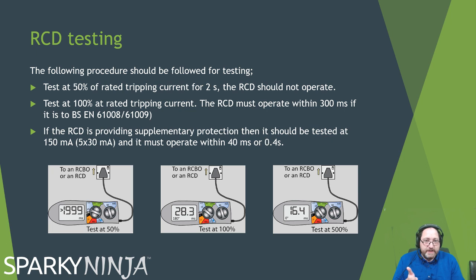300 milliseconds is going to be your 61008, 61009 at times 1. Times half should be no trip. Times 5 is only if you're actually testing an RCD that's been installed for the purpose of additional protection. So if the RCD there hasn't been installed for additional protection, you don't times 5 test it. So people can be confused with that. Okay, but if you are times 5 testing it, then we know that 415.1 says 40 milliseconds, so it should be disconnecting within 0.04 of a second. Okay, fairly easy to do.